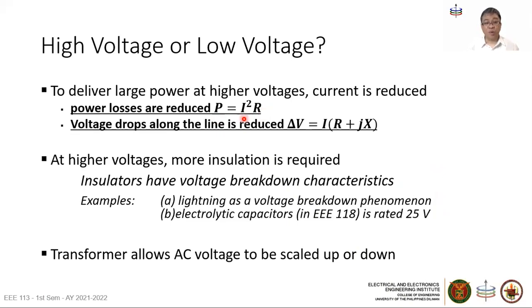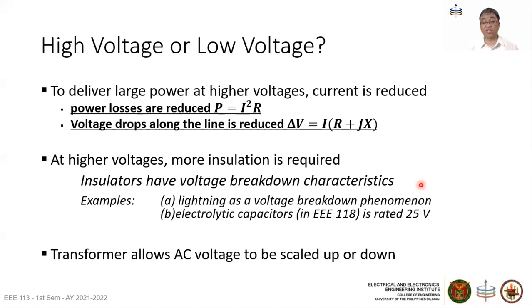The voltage drop across the line is also proportional to the current, so reducing current reduces voltage drop. Can we increase voltage to much higher levels? The Philippines has 500 kilovolts, while China has 1,000 kilovolts transmission lines. At higher voltages, more insulation is required — for example, polymer insulation in transmission lines must be much thicker. Thicker insulation means heavier lines and stronger towers. So depending on the amount of power to transmit, we decide on optimal voltage levels using standardized values.